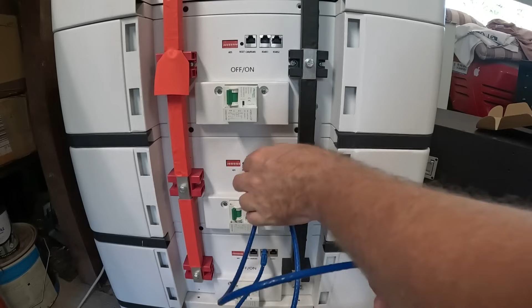So to upgrade the firmware on these version 3 BMSs, we have to disconnect all the communication first, because we need the RS485 ports on the back here to update the BMS. And if there's one cable still connected to another BMS, then it won't update. In fact, it won't even connect your computer software to your BMS. So you need to interrupt the communication to any other BMS while you're doing this.